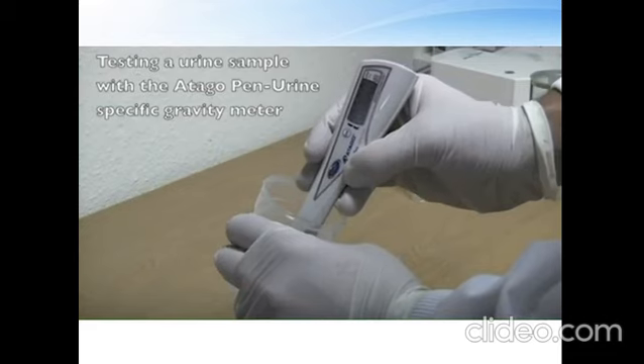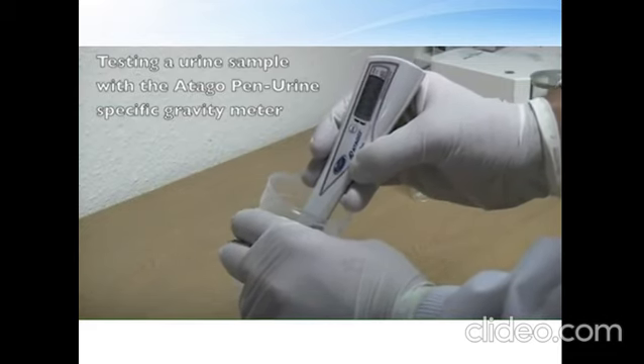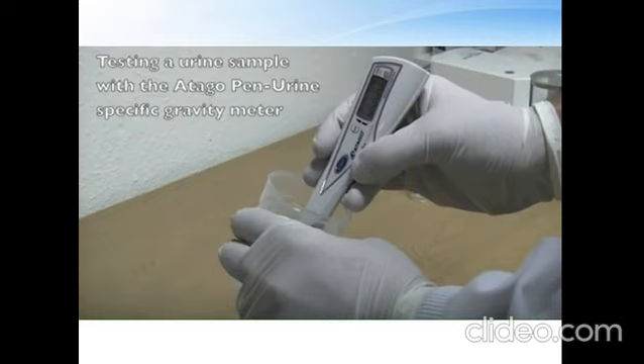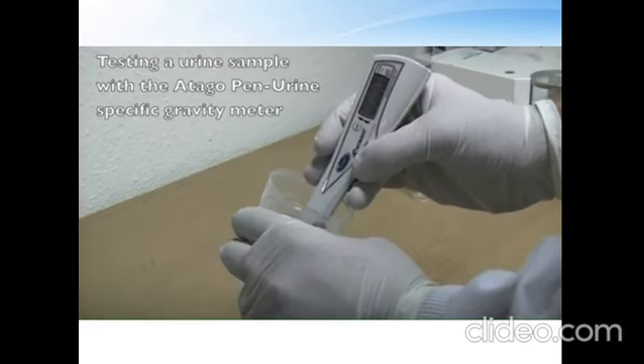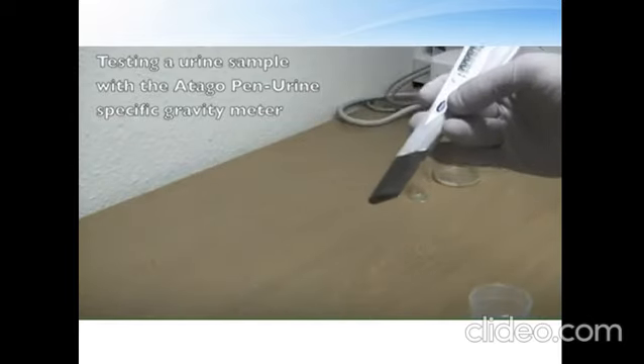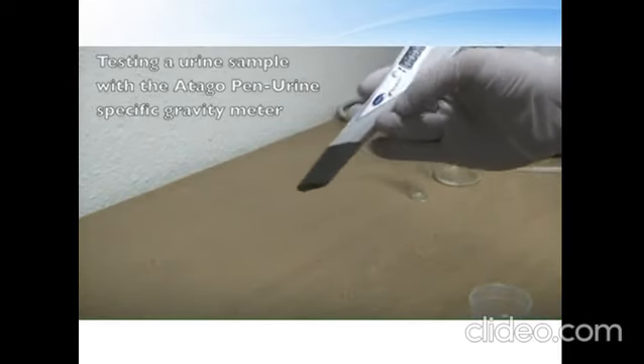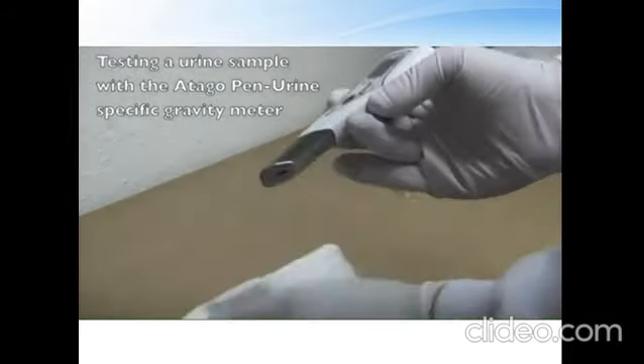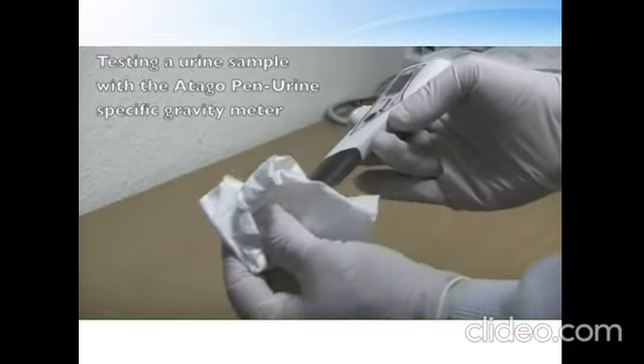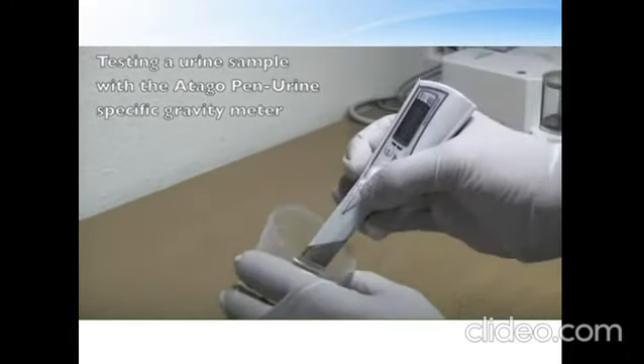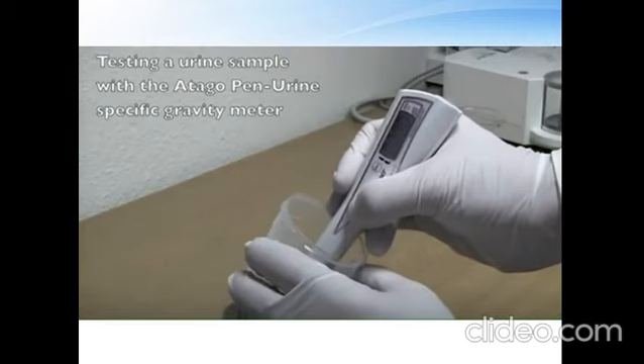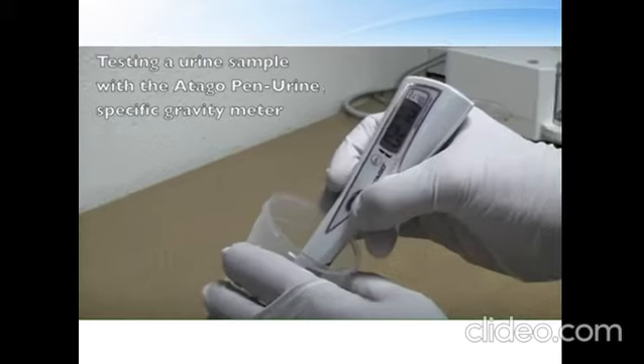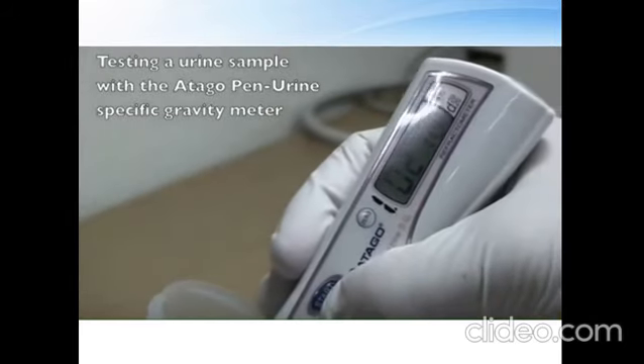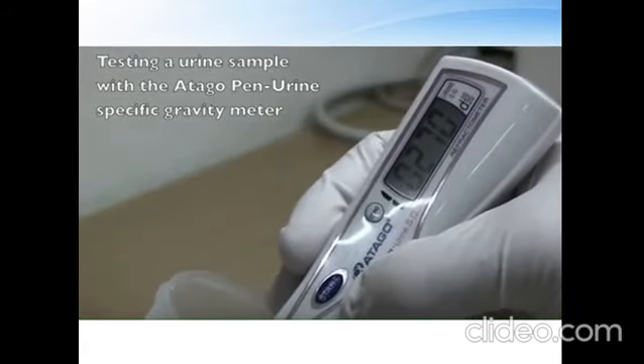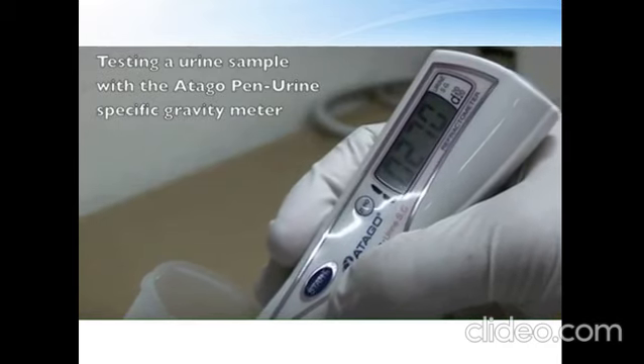The value expressed is for water, 1.000. The tip may now be dried. The probe is now put into the urine sample. Pressing start activates the read cycle, and the value is shown within 2 seconds.